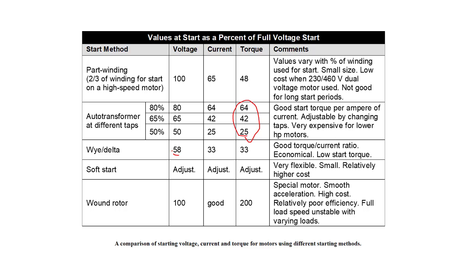Wye delta? Well, we reduce the voltage because we're only going to be down to 120 divided by 208, right? So that's 57.7%, or 1 divided by root 3. So voltage is down to 57.7%. We know that the current's going to be a third, or 33%. Basically if we take 0.577 and square it, that is also 33.3%. So it too is proportional to the square of the voltage reduction. 57.7% squared is 33%. And because our voltage is down and our current is down, our torque produced is still proportional to the square of the voltage reduction. So in Y delta, it's a little bit easier. It always works out to 1/3 of the normal full voltage starting torque, or 1/3 of the normal full voltage starting current.